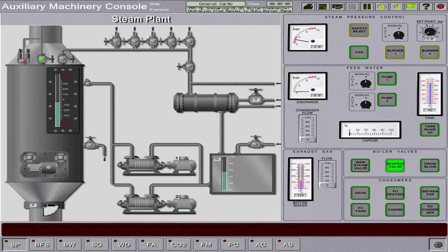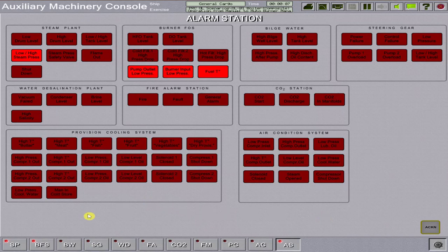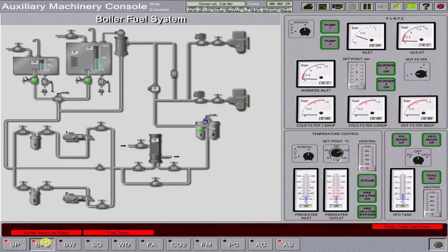Let's start the simulation. I'm going to demonstrate how to operate a cold state fire tube boiler going to normal running condition. First, we need to acknowledge the alarm on the alarm station. Then proceed to the steam plant page and prepare your boiler by pressing the fan button on the steam pressure control. Then close the boiler aerating valve.